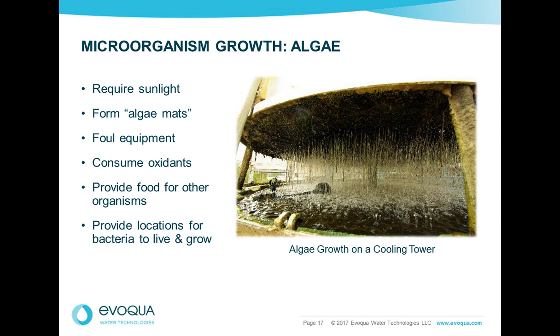Microbiological growth, you could have algae. The easiest way to prevent the algae is cover the deck. However, sometimes that's not practical. Algae requires sunlight to live, so if you cut off the light, algae can't form. Algae mats can foul equipment, and it can even be a safety hazard. Algae is slippery. If you're walking on the deck, you can fall down, and sometimes falling off a cooling tower is a long fall.